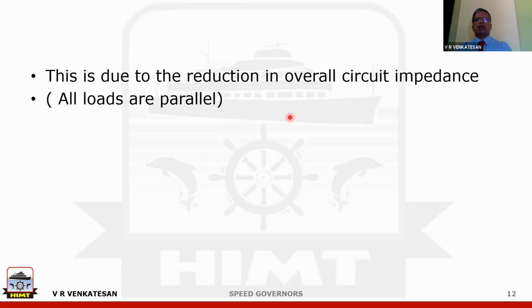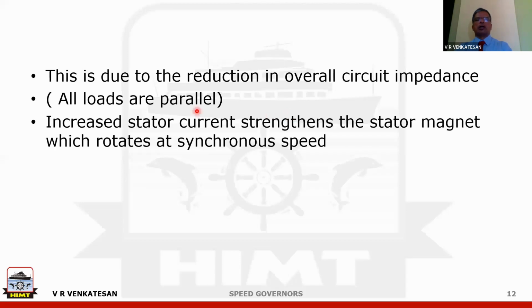So all loads that you are connecting, whether when one motor is running and you start another motor, all loads that are connected are always connected in parallel. So because loads are connected in parallel, the overall impedance in the circuit will come down. And since the overall impedance is coming down, current will start increasing. So this is the simple principle by which when you add more load, the alternator current increases. So when the alternator current increases, the next part is that the stator magnet will become stronger.